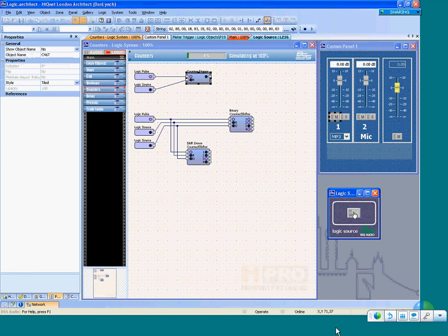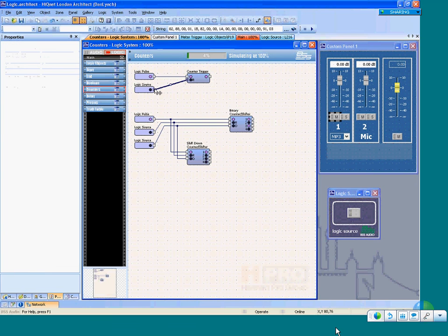So here we go. Turn off the reset. There's 1 pulse, 2 pulses, 3rd pulse, and the output turns on. So you can keep track of events that way. If you want something to happen on every 3rd pulse, for instance, or every 20th pulse or whatever, in this case we'll call it 3rd pulse, I already have it wired up that way, or programmed that way, I can wire the output straight back to the reset. Move this out of the way so you can see.